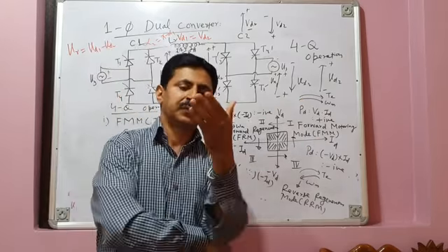Now I want reversal of the motion. I want the machine to go from forward motoring mode to reverse motoring mode. I cannot do that directly. I cannot go from quadrant 1 to quadrant 3 directly. I have to go through quadrant 2. In quadrant 2, regenerative braking should take place. My machine should operate in forward regeneration mode. That is mode 2, forward regeneration mode.